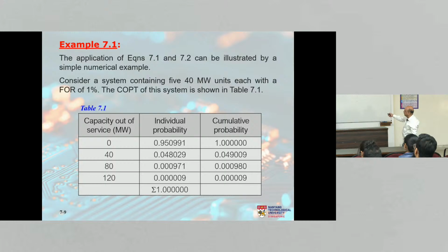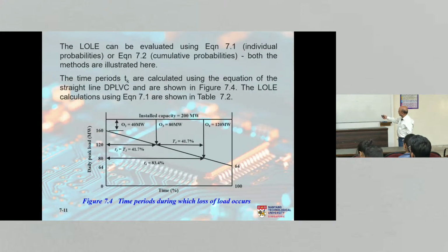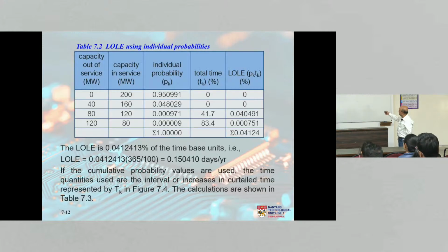So I know the probability. What do I need? I need T2. I need the time units corresponding to 40 megawatt out. But I look at this, 40 megawatt out means I'm still able to meet 160 megawatt, correct? So therefore, I'm not losing the load at all. So that number will also be 0. That number will also be 0. The time units 0, 0. Can you see that?